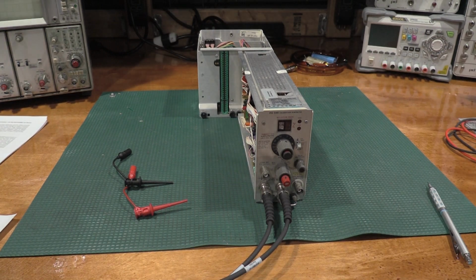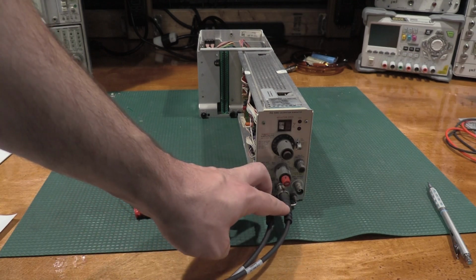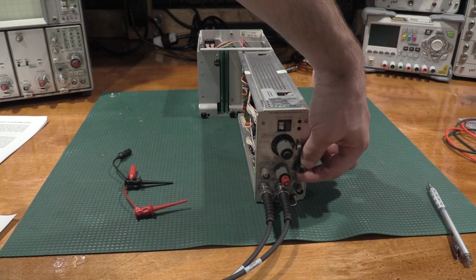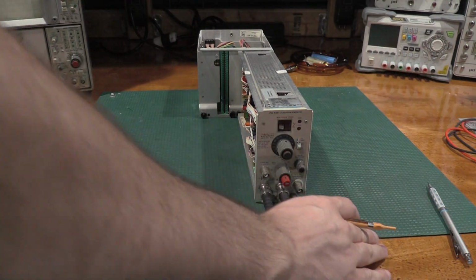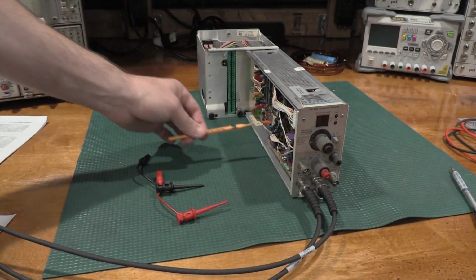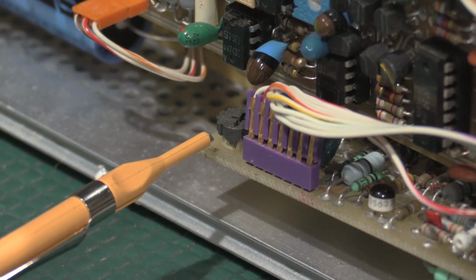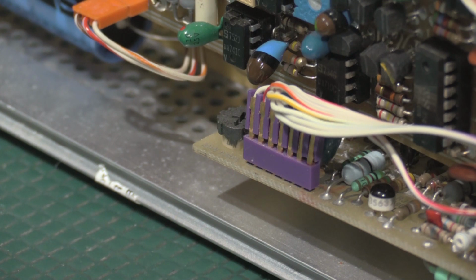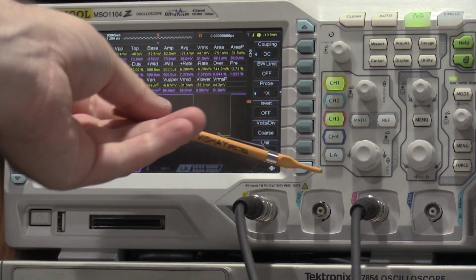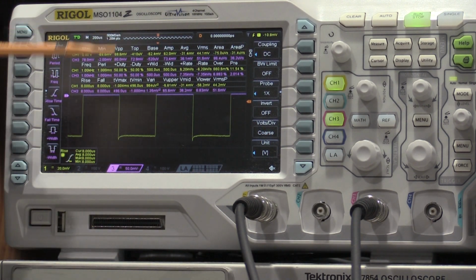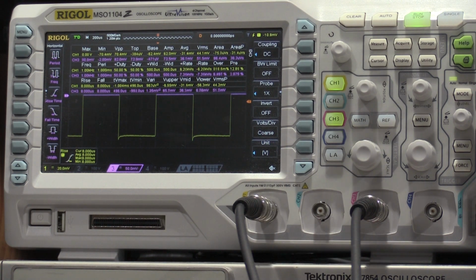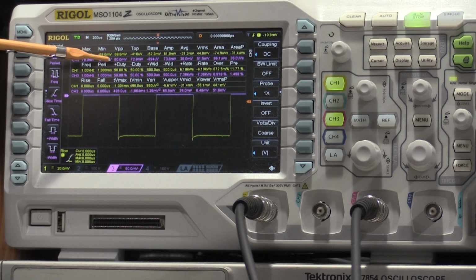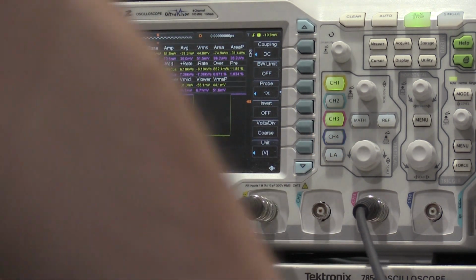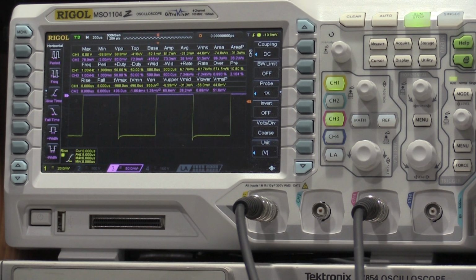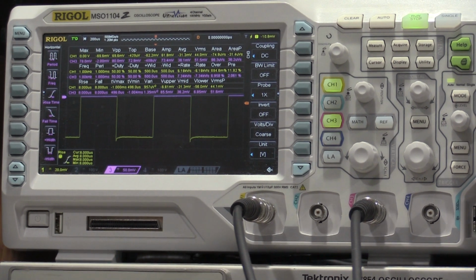Okay, this test setup's a little confusing as well. So you have both channels of the fast rise. The pulse amplitude needs to be all the way down, you're setting the pulse minimum, which is this potentiometer right here. Pulse minimum right here. But you want to measure both pulses at the same time, and you want one of them to hit 80 millivolts. I'll show you the scope. I have both cables coming in. One's on channel 3, one's on channel 1. Both are terminated into 50 ohms. Everything's on. I have measurements set up for all of the waveforms. And I was looking at peak to peak, 80 millivolts channel 3 hit first, which is for me the fast fall, not the fast rise, which is fine.